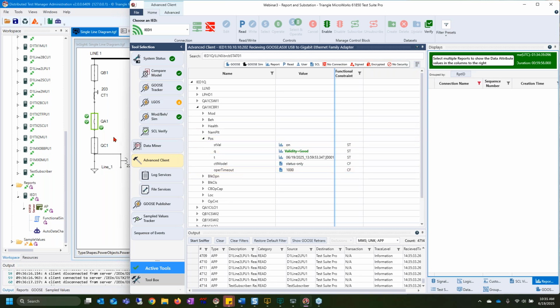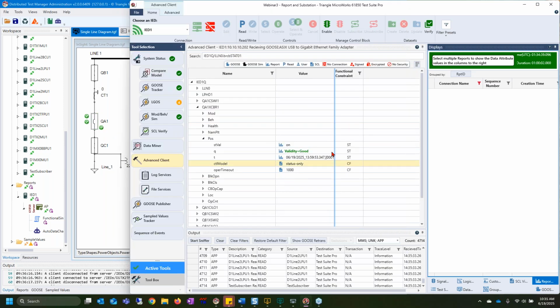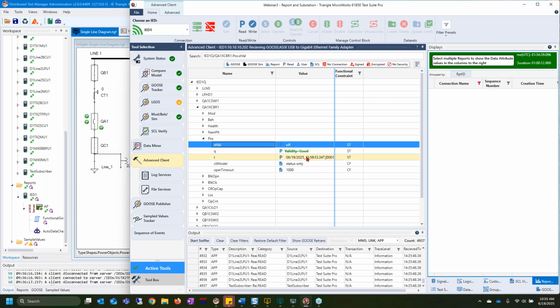So if I go down to this and simply open the breaker here, we'll see the value doesn't change right off the bat. Well, that's because I don't have reports enabled, or I don't have any sort of polling or whatever set up. So I can right click here and perform a read. And sure enough, you can see the symbol next to it has now turned to a P. That is for polling. And we can see that the value is now off. But typically you don't want to have an engineer sitting here just doing a right click and a read, or having your system continuously polling. I've done a read two or three more times since we started and nothing's really changed. We're kind of just wasting the bandwidth.